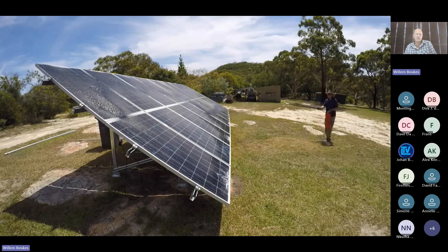What I wanted you guys to see is the electrical leakage of the system on the framework of the panels. And in this scenario, when you add water to the structure, it actually enhances the electricity flow. So your earthing component in these structures becomes very critical in making sure that these floating voltages go down to earth and protect the structure, especially in steel structures where you have a live DC structure and where you also have to integrate fire sprinkler systems. You're actually making the whole structure live with DC voltages. So your earthing component in these solar systems becomes critical, making sure that these systems are protected against DC arcs forming.